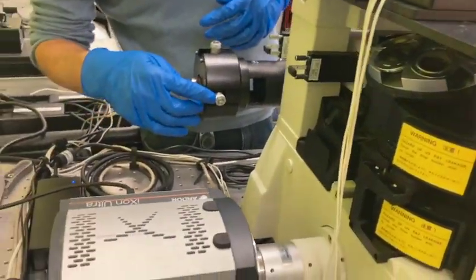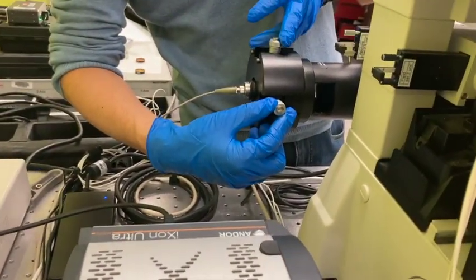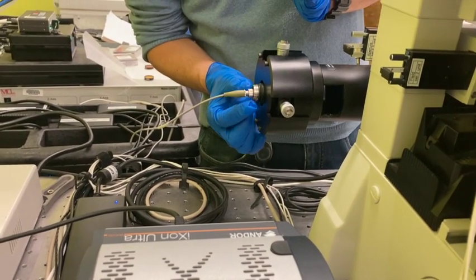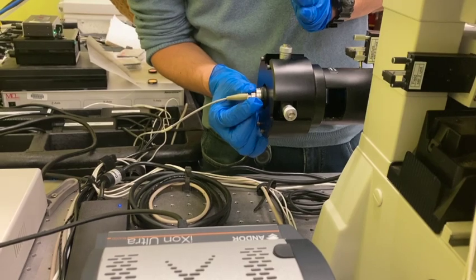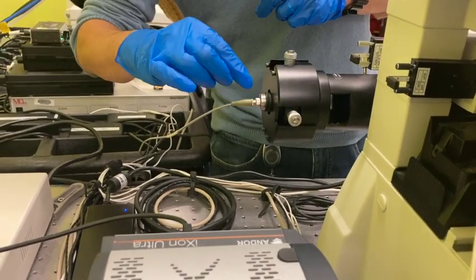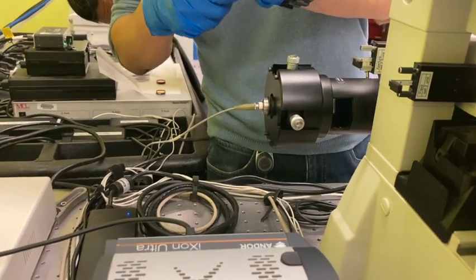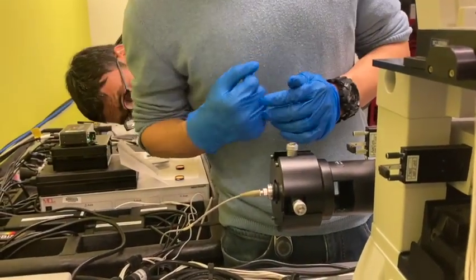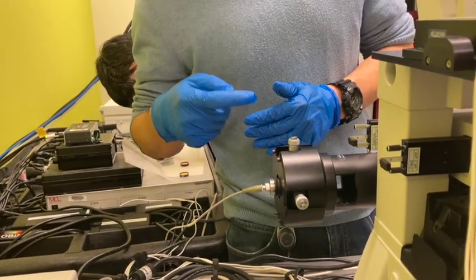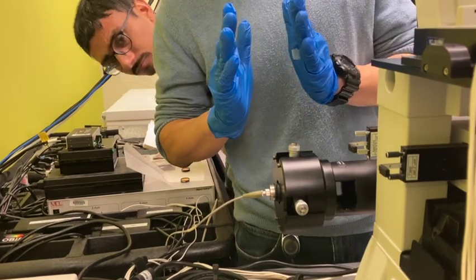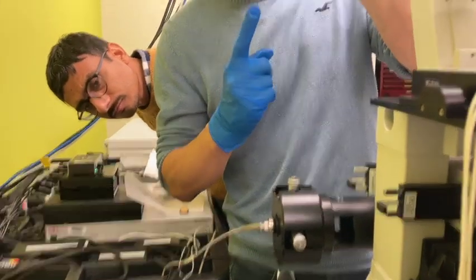We have this one and this one to adjust the position of this fiber. So when you're moving this and this, you're going to change the position of the fiber, up or down.